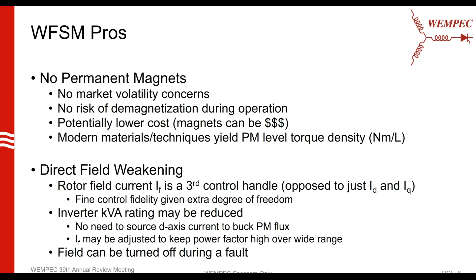The disadvantages for this machine are that there's added rotor mechanical complexity. So you have coils instead of permanent magnets. That's harder to do mechanically. They have to be wound, inserted. There's wire integrity, both at speed and wire insulation, and they must be cooled because you're generating I²R loss on the rotor. So you also have to supply power to the rotor, adding a power supply for the rotor, and so this is traditionally done with brushes and slip rings, and that's a reliability concern. But brushless excitation approaches are more complicated, but we need to use them because brushes are just not going to be compatible with modern systems. You need to make it brushless, and the cost of the excitation system must be less than the magnets that you're replacing.